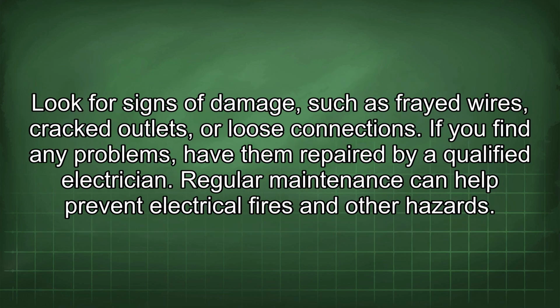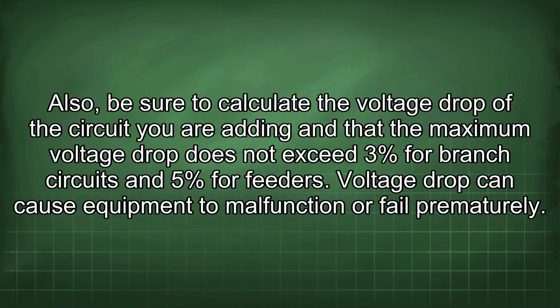Look for signs of damage, such as frayed wires, cracked outlets, or loose connections. If you find any problems, have them repaired by a qualified electrician. Regular maintenance can help prevent electrical fires and other hazards. Also, be sure to calculate the voltage drop of the circuit you are adding and that the maximum voltage drop does not exceed 3% for branch circuits and 5% for feeders.